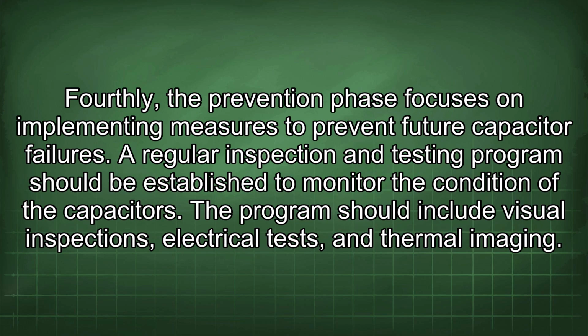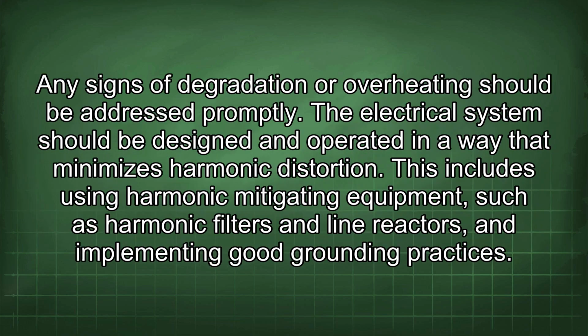Fourthly, the prevention phase focuses on implementing measures to prevent future capacitor failures. A regular inspection and testing program should be established to monitor the condition of the capacitors. The program should include visual inspections, electrical tests, and thermal imaging. Any signs of degradation or overheating should be addressed promptly.